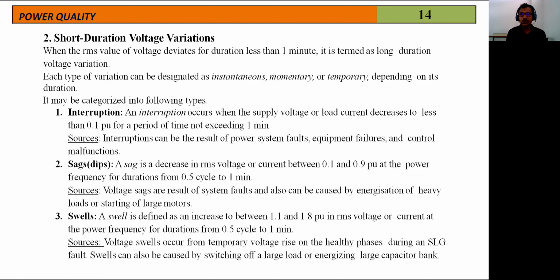If it is less than 0.1 per unit, that is called an interruption. If it is between 0.1 and 0.9 per unit, then it is called a sag, either voltage sag or current sag, which lasts for a duration of 0.5 cycle to 1 minute. Maximum half cycle or maximum up to 1 minute. That is called a voltage sag or voltage dip.